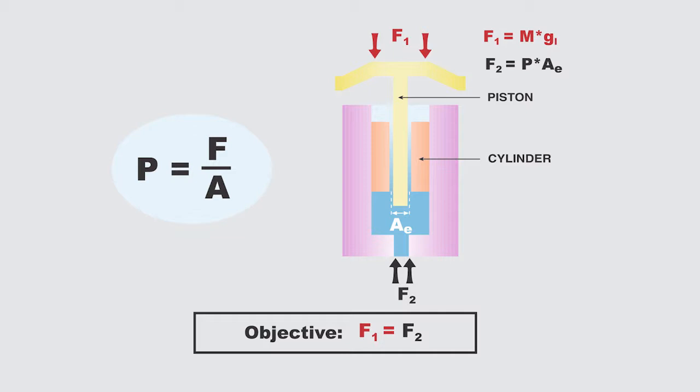Perhaps the biggest is the local acceleration of gravity. Pressure is defined as force divided by area. With a pressure balance, the force in question is the force generated by the masses being accelerated downwards by gravity.